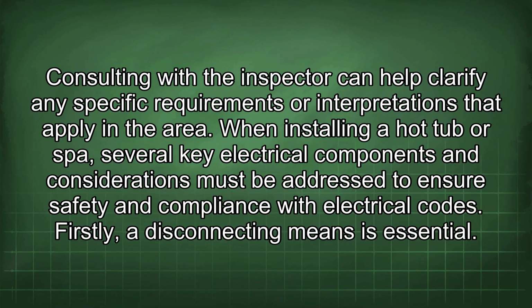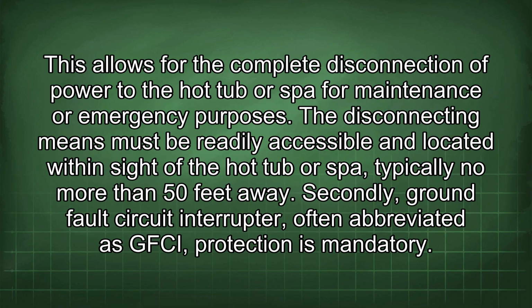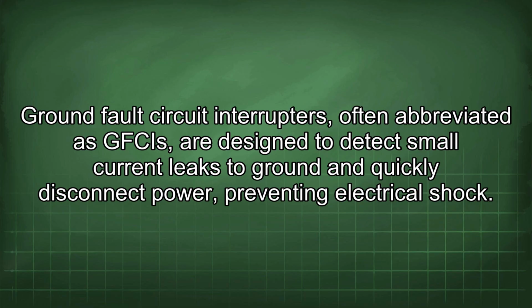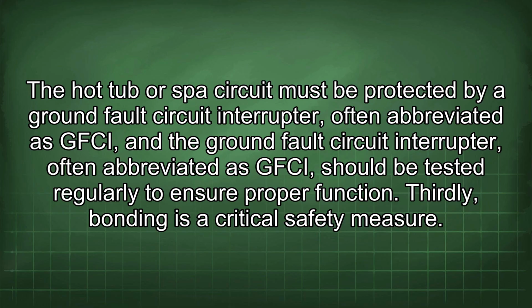When installing a hot tub or spa, several key electrical components and considerations must be addressed to ensure safety and compliance with electrical codes. Firstly, a disconnecting means is essential. This allows for the complete disconnection of power to the hot tub or spa for maintenance or emergency purposes. The disconnecting means must be readily accessible and located within sight of the hot tub or spa, typically no more than 50 feet away. Secondly, ground fault circuit interrupter, or GFCI, protection is mandatory. GFCIs are designed to detect small current leaks to ground and quickly disconnect power, preventing electrical shock. The hot tub or spa circuit must be protected by a GFCI, and the GFCI should be tested regularly to ensure proper function.